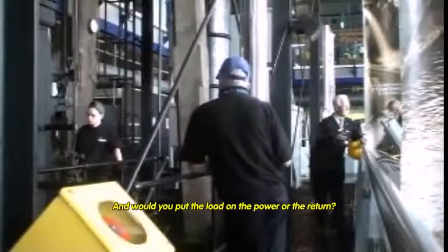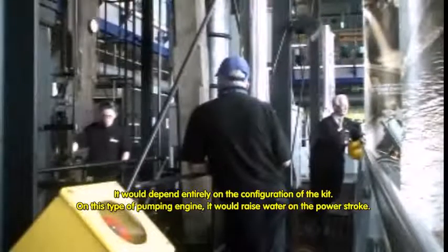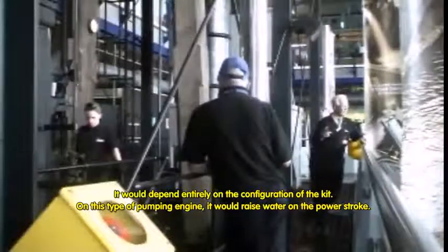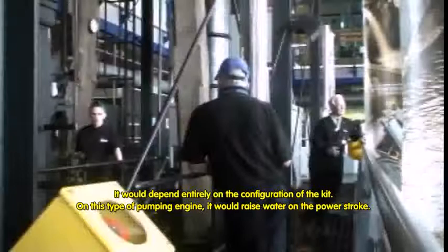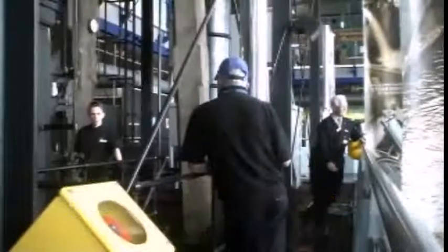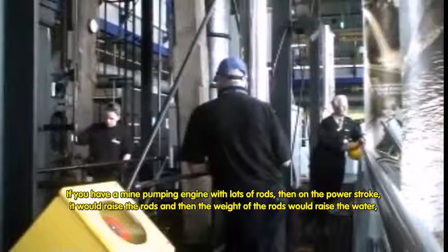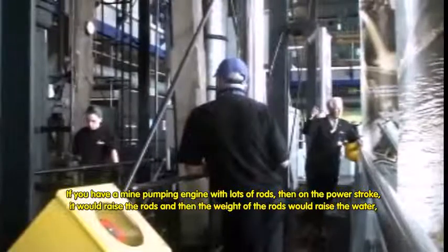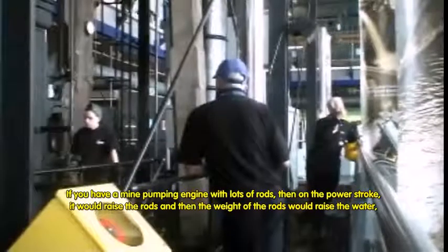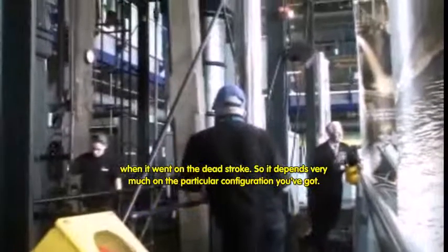Would you put the load on the power or the return, the vacuum side? It would depend entirely on the configuration of the kit. On this type of pumping engine, it would raise water on the power stroke as the piston goes down. If you have a mine pumping engine with a lot of rods, on the power stroke it would raise the rods and then the weight of the rods would raise the water when it went on the dead stroke. So it depends very much on the particular configuration.